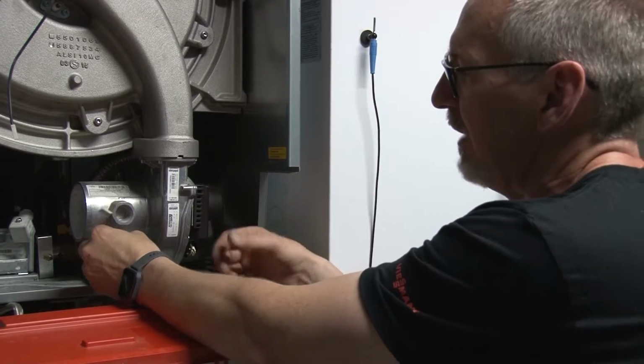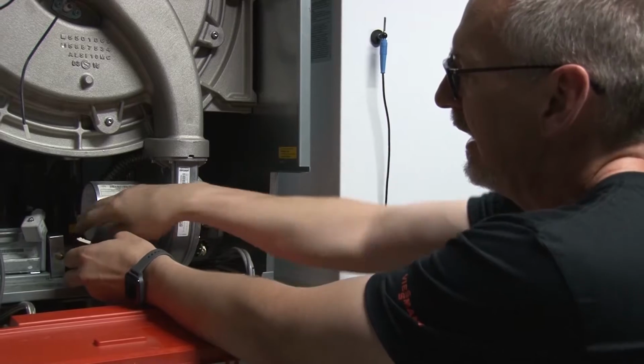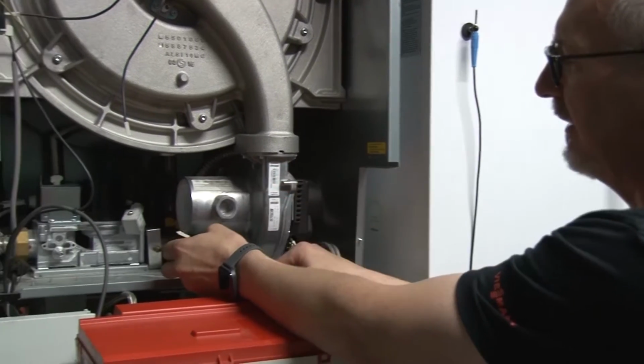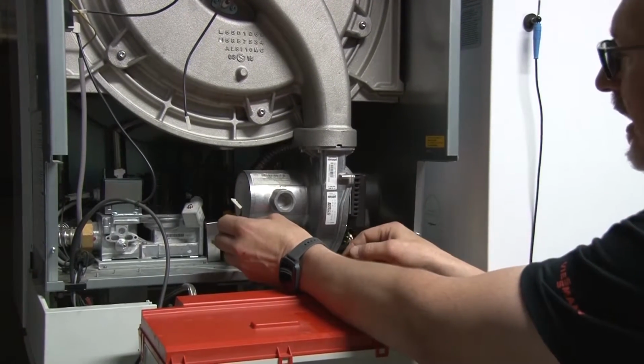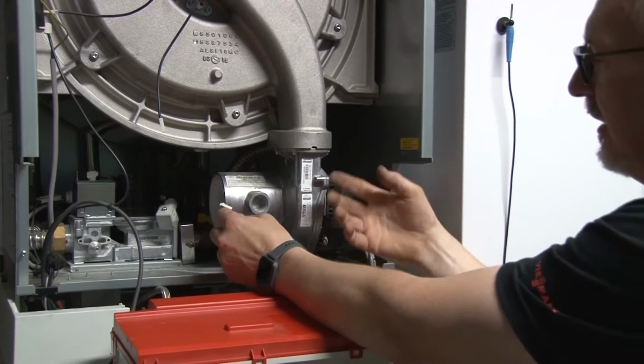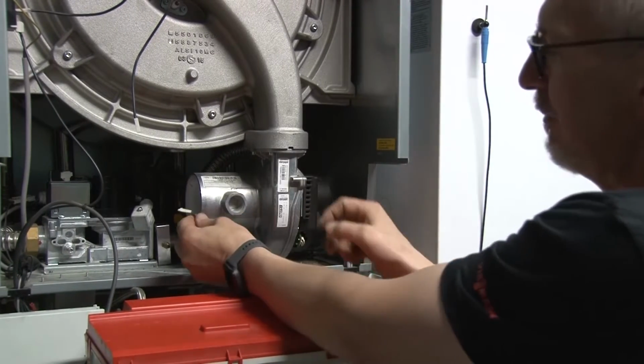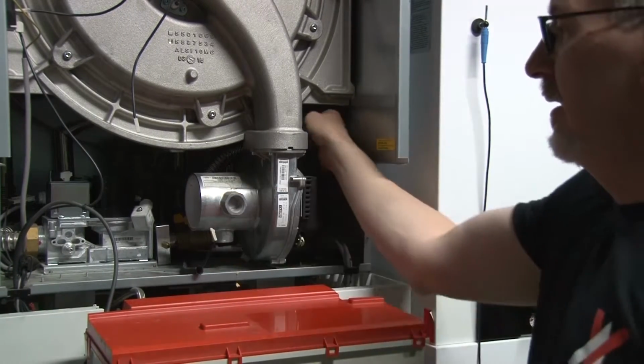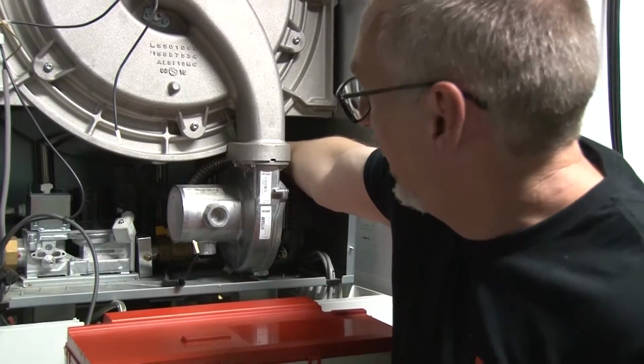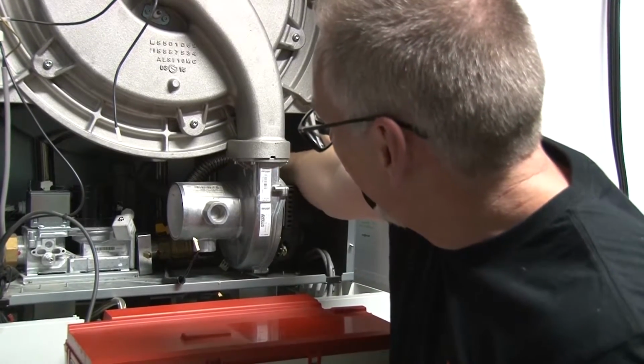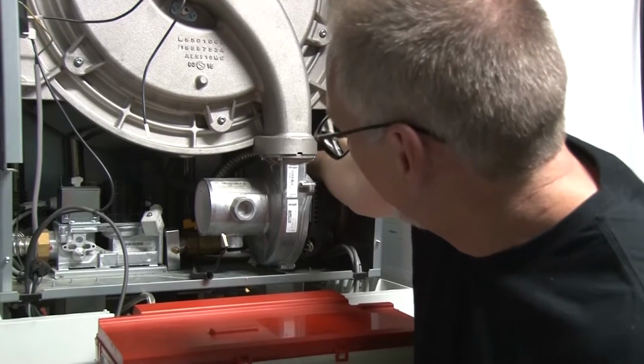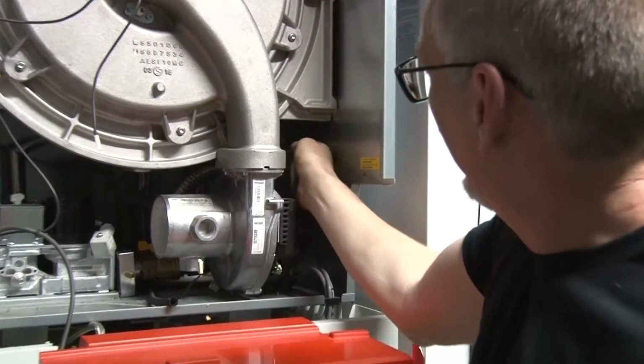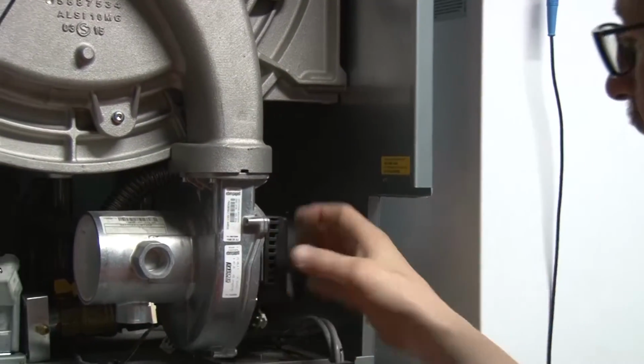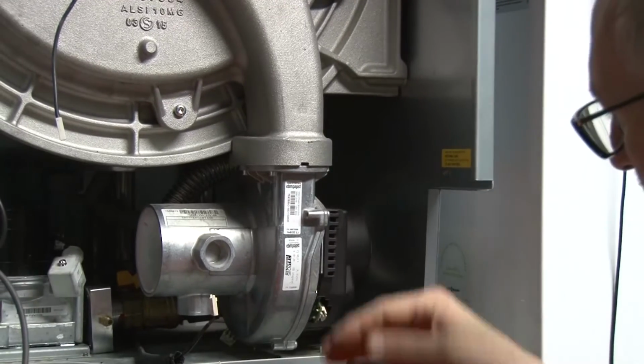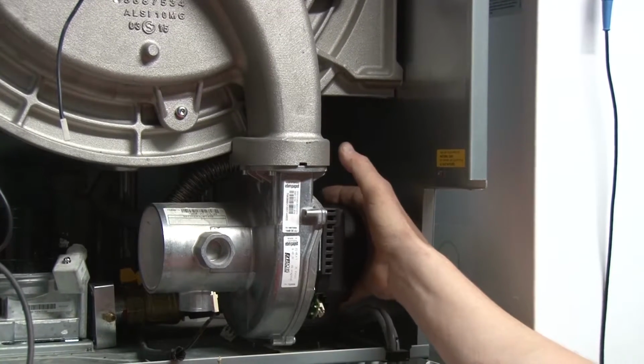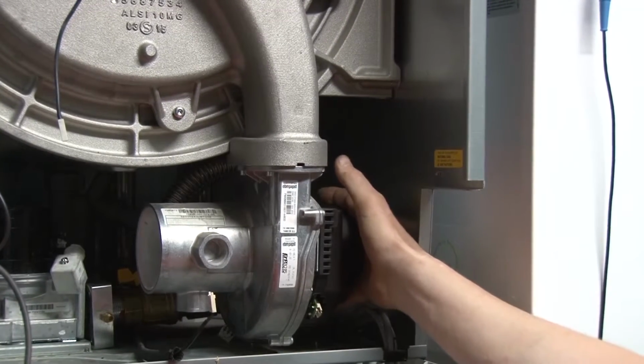So the higher the fan speed, the more gas is being pulled in and sucked into your venturi here. We're going to have a look at that in conversation about venturi in a second. And of course, the lower the fan speed, and that's the pulse rate of this 100A plug, the lower the burner firing rate is going to be. And on the back side, there is another plug. It's the 100 plug. We'll see that in a second when I pull the burner out. And that's basically the power to the fan, 120 volt AC to this particular fan.